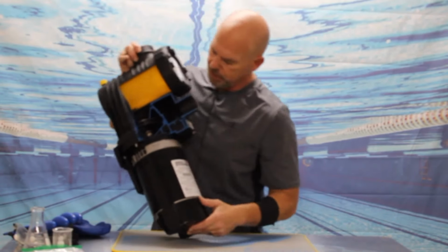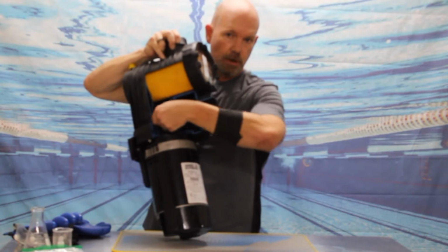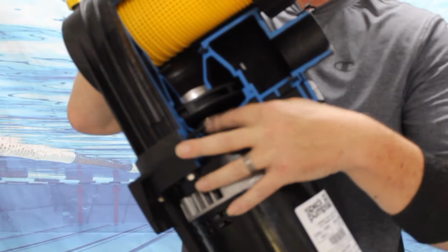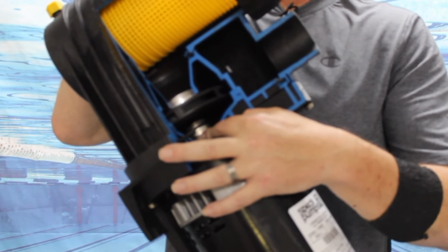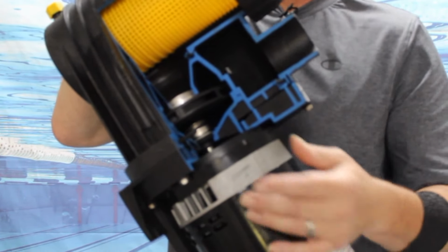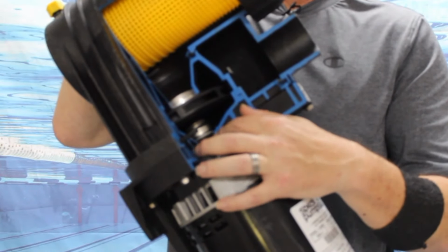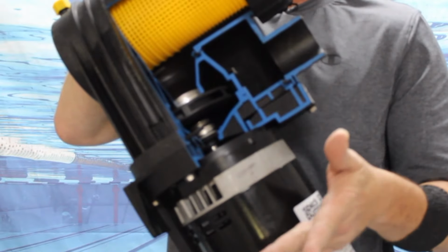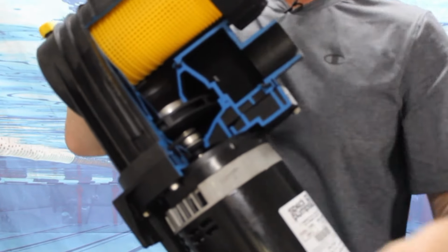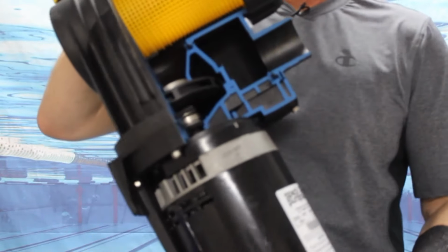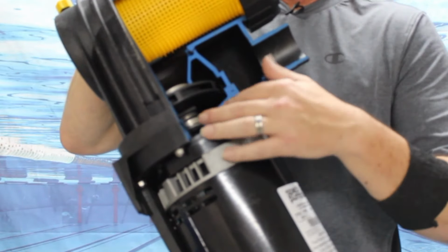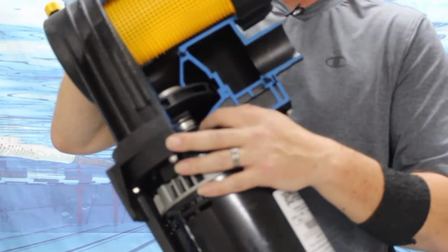So if I take my pump here, this is the impeller. That's the part of the pump that actually throws the water. This spring-loaded piece behind here, that's your pump seal. The pump seal is the furthest point back in the system that you could have a suction side leak. It's also the only place in the system where you can have a suction side leak that'll draw in air and drip water. All the remainder of the suction side leaks you could possibly have from the pump housing forward will only draw in air while the pump is running. However, this, if it fails, will allow the system to draw in air and drip water at the same time.